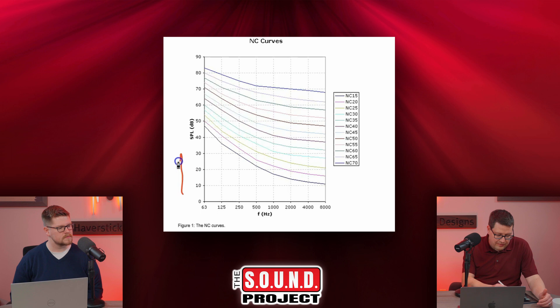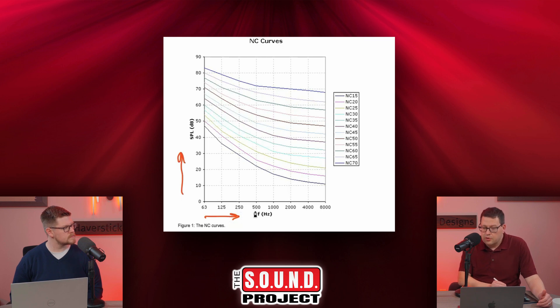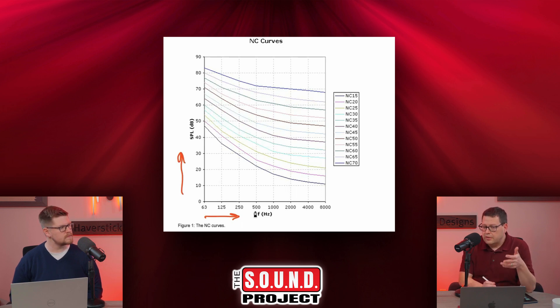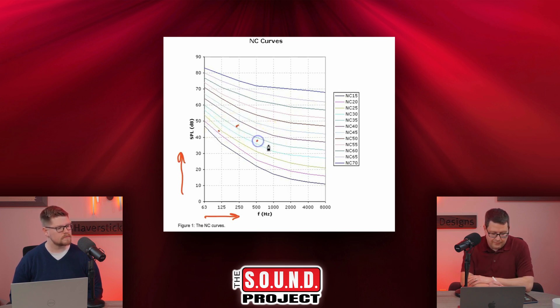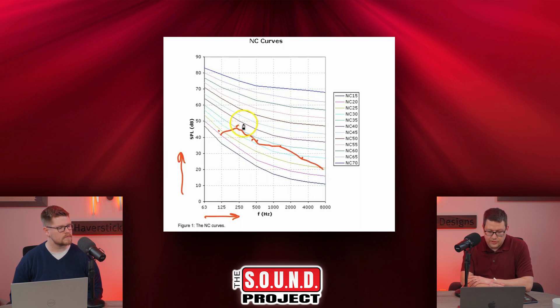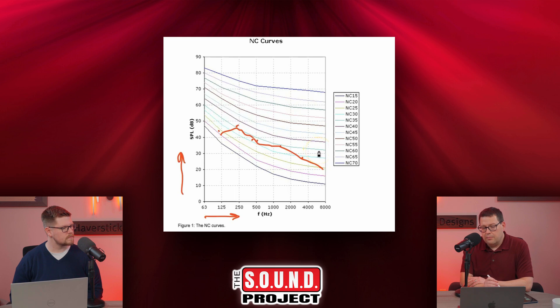I actually have a graphic here that we can share. This is a standardized NC curves graph. On the Y-axis we have SPL in decibels, and on the X-axis we have frequency in hertz — going from low frequencies up to higher frequencies. What you do is measure a room's ambient noise with the HVAC running, plot those points on the graph, and draw a line to connect them. Wherever that line crosses the highest NC curve — in this example it crosses the light green NC35 line — that gives you your NC value.